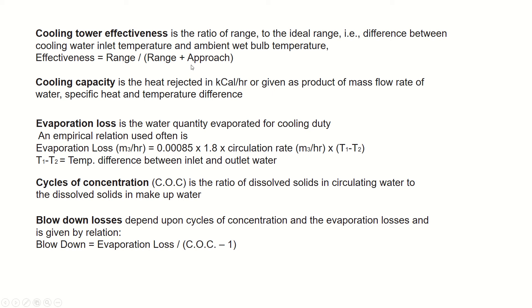This gives a result in terms of percentage. The second performance criterion is cooling capacity — the heat rejected in kilocalories per hour, given as the product of mass flow rate of water, specific heat, and temperature difference. We calculate cooling capacity by multiplying mass flow rate of water, specific heat of water, and the temperature difference between inlet and outlet.